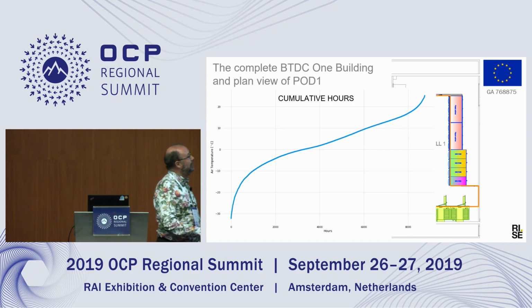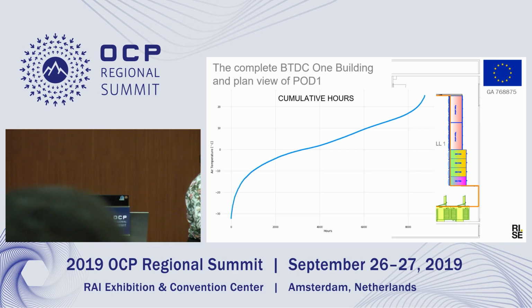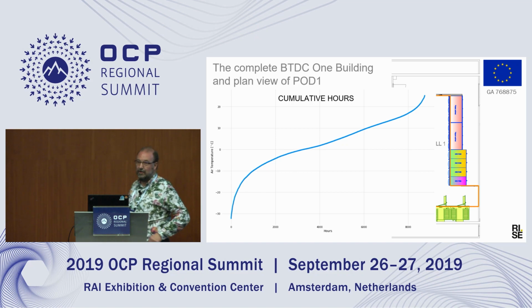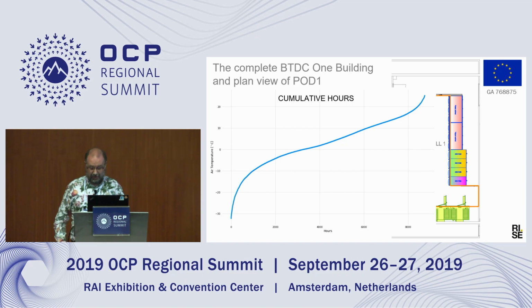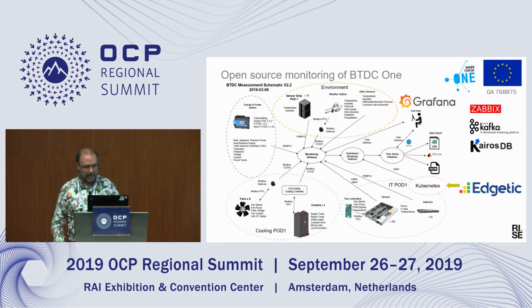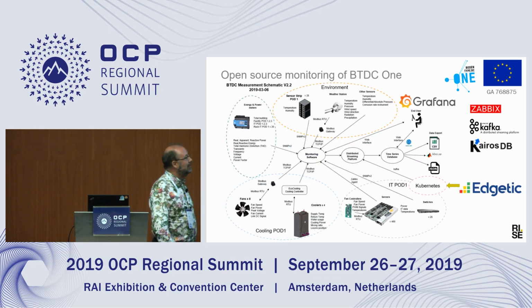This issue of free cooling using fresh air—this is a cumulative plot for the site showing the number of hours in the year, around 8,600 hours total, below zero. It shows about 3,000 hours per year are below 0 degrees centigrade. IT equipment is comfortable at 20 degrees centigrade, and even there, more than 8,000 hours per year are below 20 degrees outside. So it's a very efficient way of using the local climate to cool the IT.